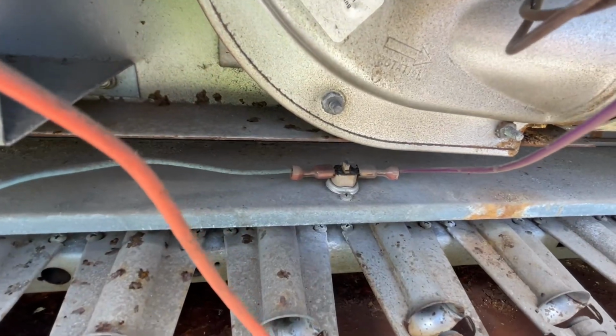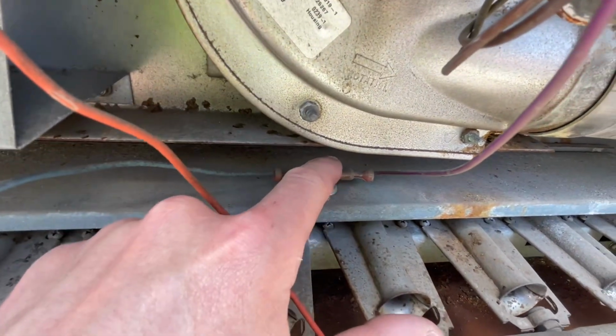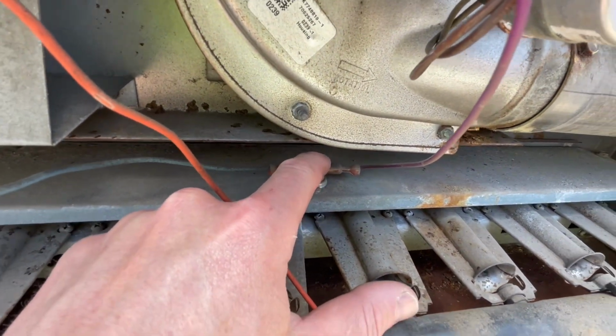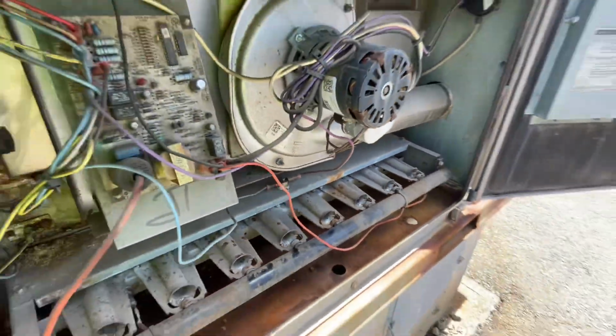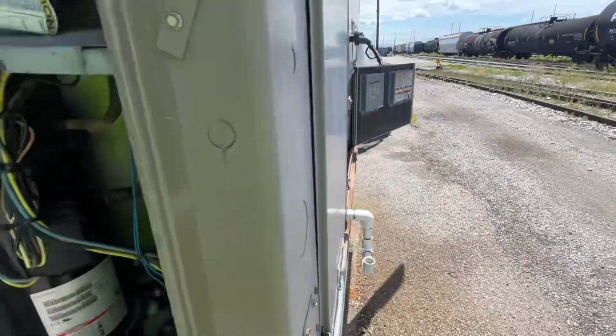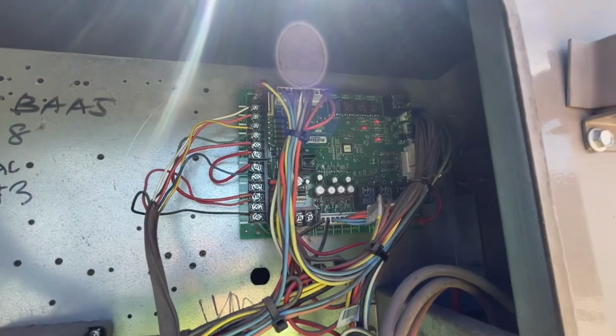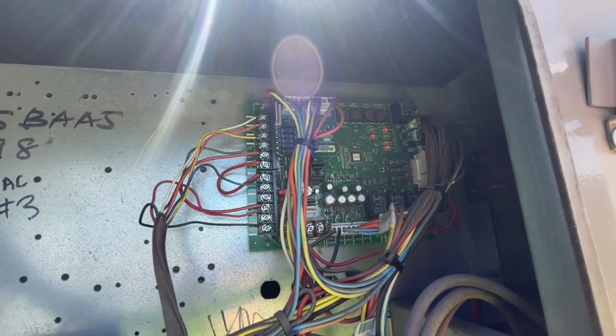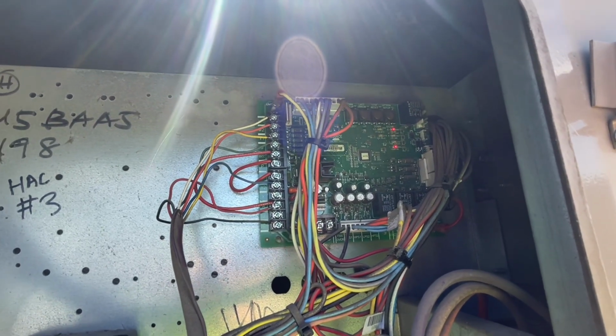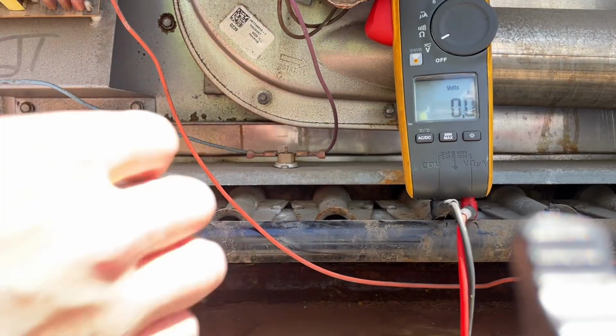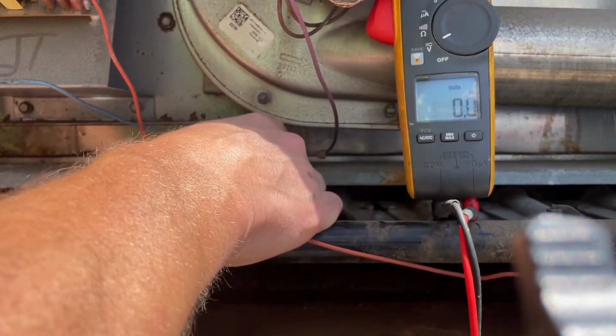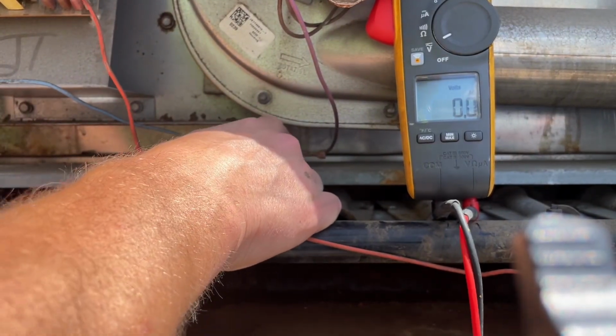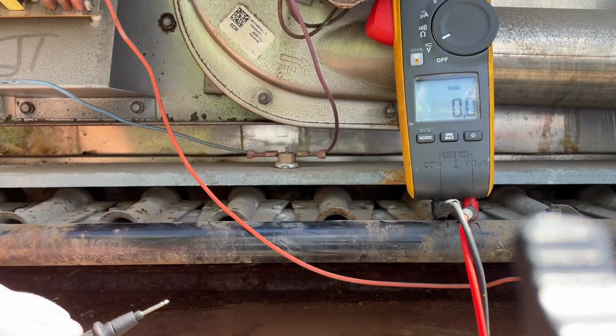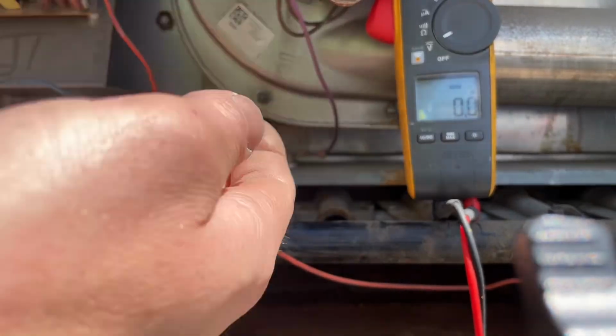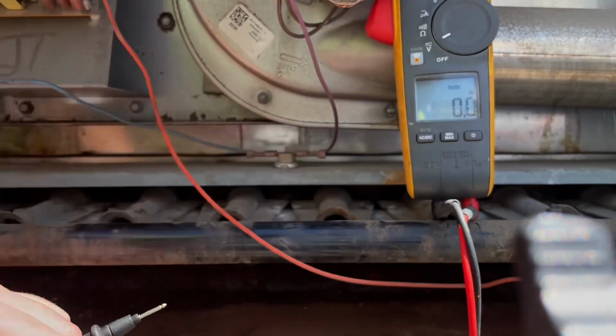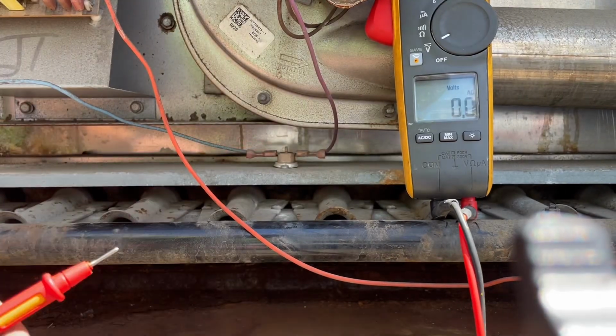Yep, and wouldn't you know it, I just felt that click down. But let's go back to our main panel, see if our code has eliminated itself, which it has not. So we're gonna check for our high limit next. So I just reset this rollout. You can actually physically feel it click in. It's just a thermal disc that will pick up if the flames come back out, and this will open up. It's a safety procedure, but with your meter, this is how you're gonna check.